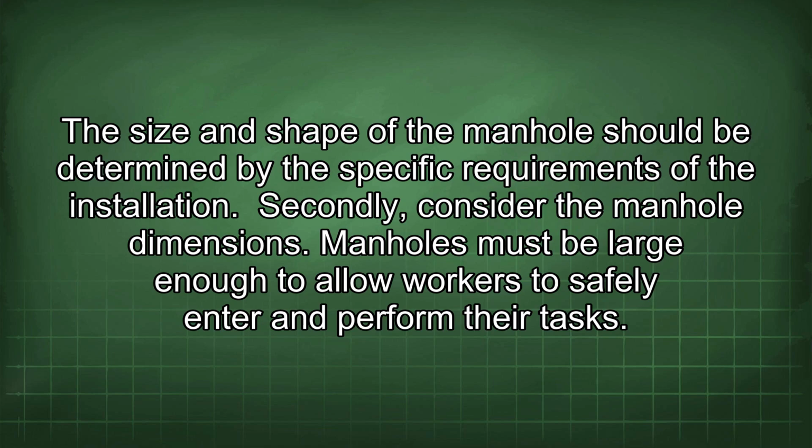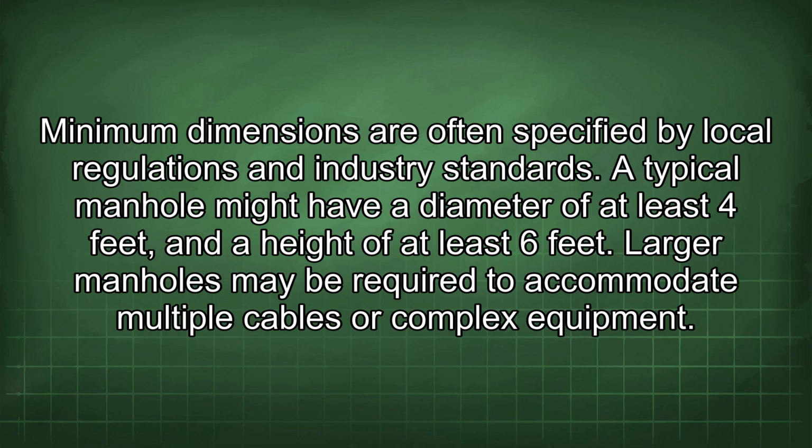Secondly, consider the manhole dimensions. Manholes must be large enough to allow workers to safely enter and perform their tasks. Minimum dimensions are often specified by local regulations and industry standards. A typical manhole might have a diameter of at least 4 feet and a height of at least 6 feet. Larger manholes may be required to accommodate multiple cables or complex equipment.